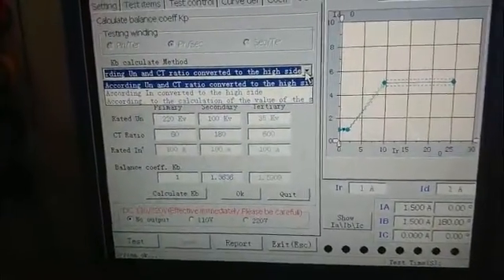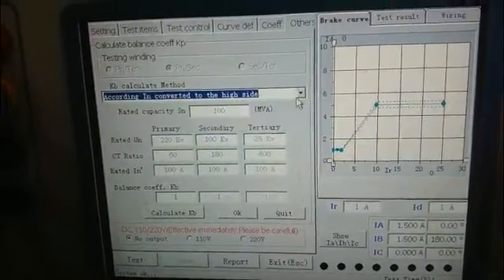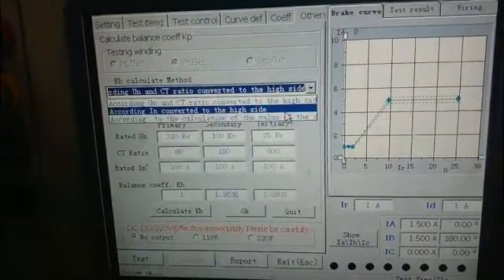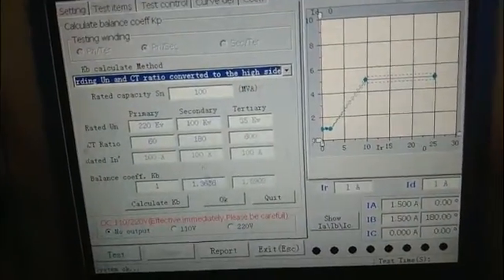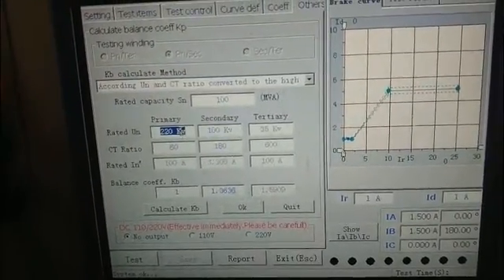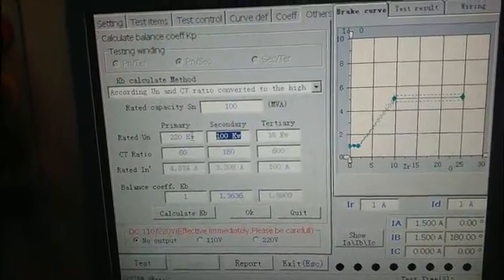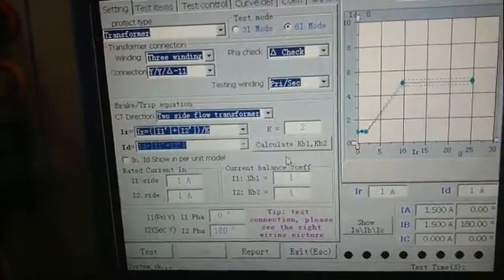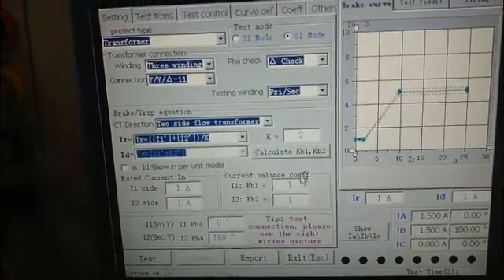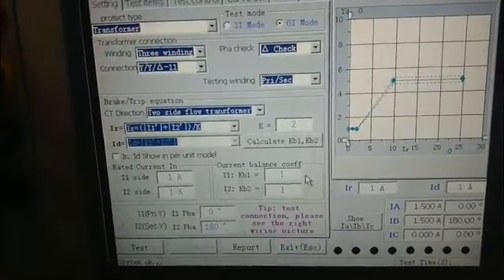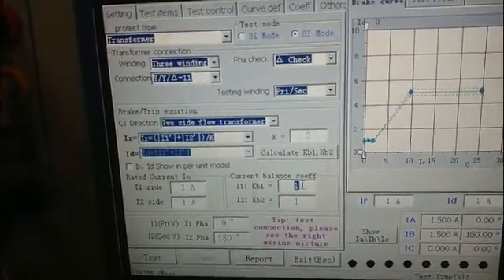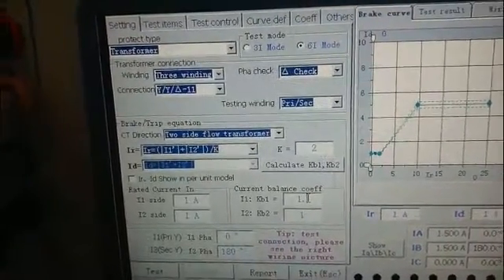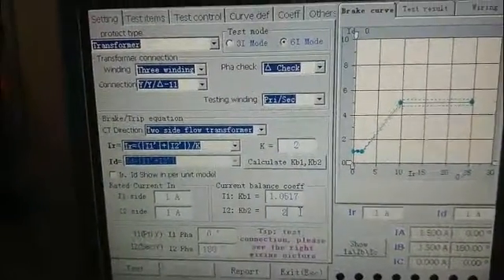Calculate the first two are the calculation to the high voltage side. Different factory has different test modes. Sometimes the protective device has its own balance coefficient. We only need to input the value directly. Now we input the high voltage side is 1.0617 and the middle voltage side is 2.1718.